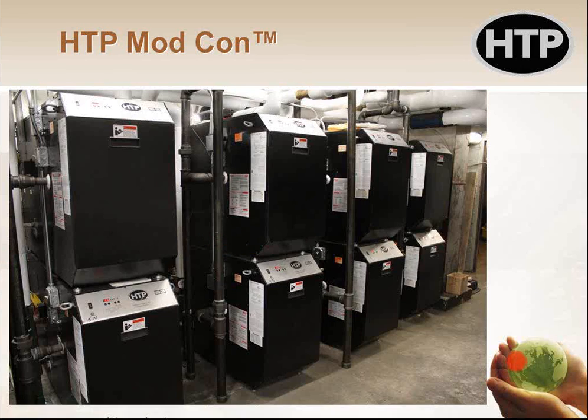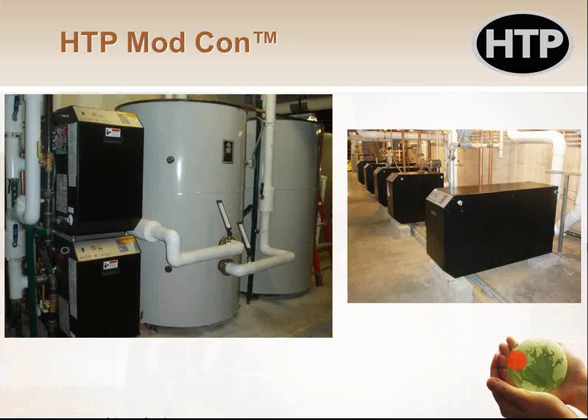There's also some boilers that do domestic water on this same building. Same boilers we used, just piped them up to the domestic plant instead. But you can fit a lot of stuff in a small space. The reason we went this way on this job, other than the rebates, was that all these boilers were up in the penthouse of a 20-some story building, and these boilers fit nicely up the elevator. They're all about 3 feet high, 2 feet wide, and they just get a little bit deeper as you get to the bigger sizes. So they fit up a typical elevator very nicely.